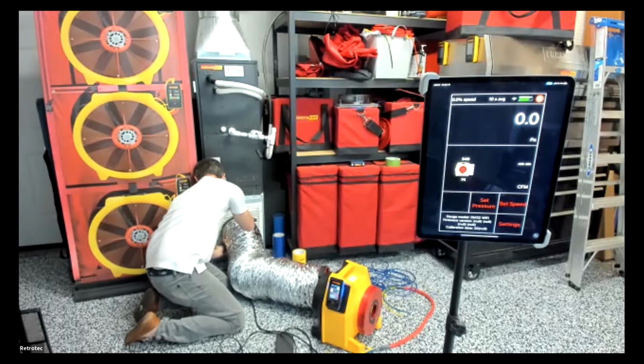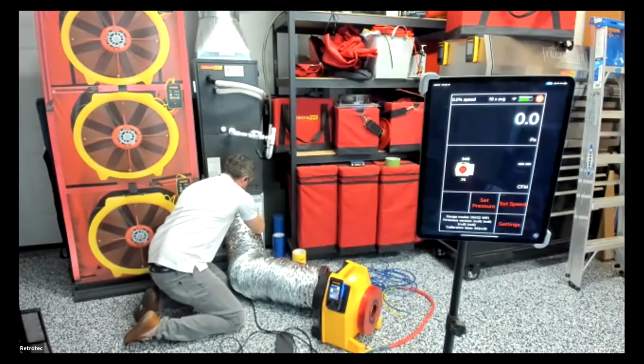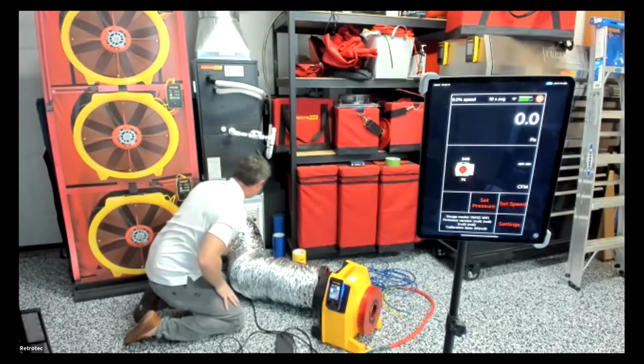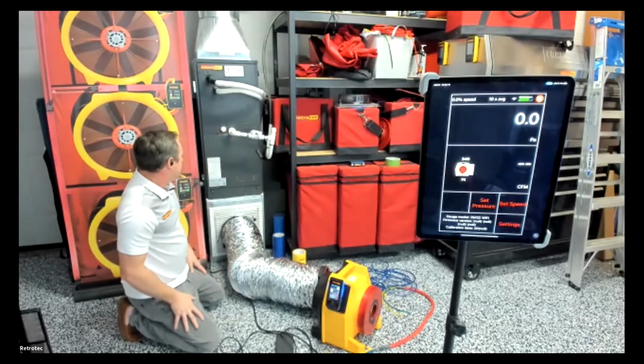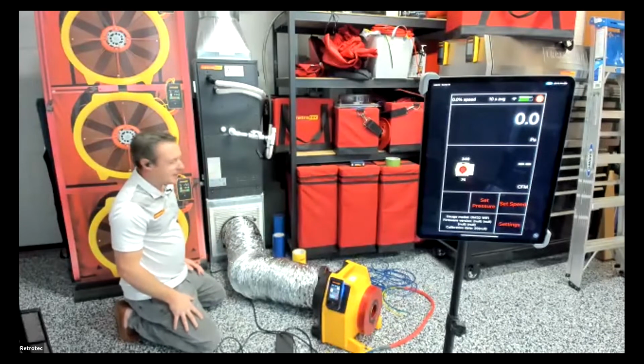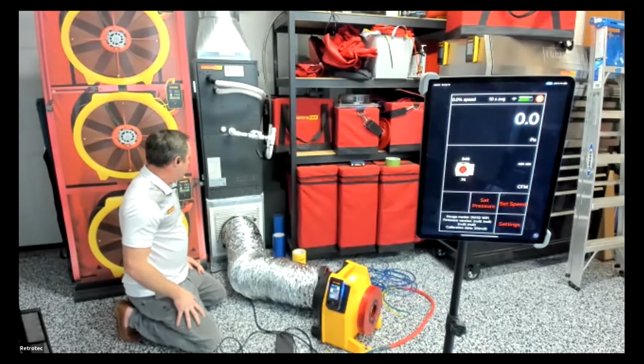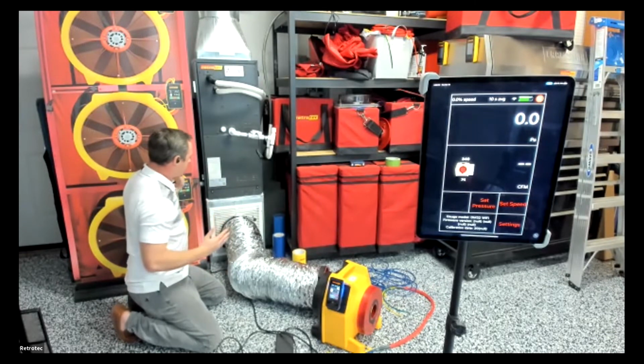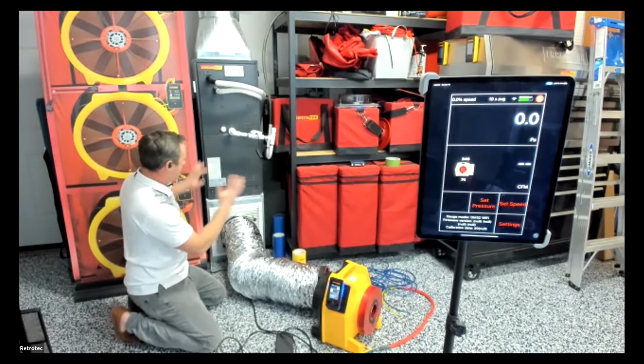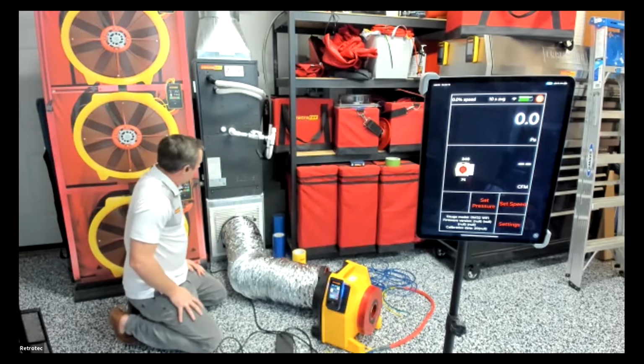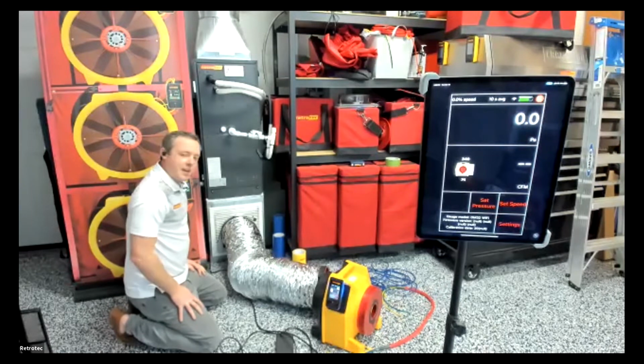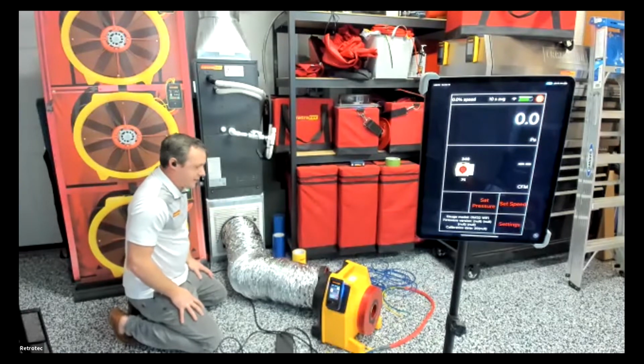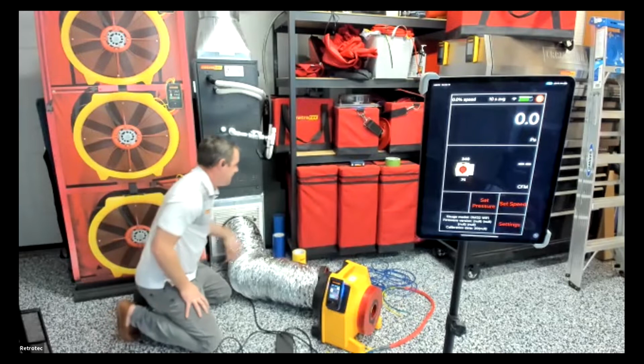There are some cases where you may want to attach this to the air handler itself. Say you don't have good return access, you can do that too. What some folks do, they'll take the service panel off and then either come up with their own panel out of cardboard or plastic, or just tape the flange in there and make sure you have a good seal. So those are the two most common ways we're going to attach this duct tester to the duct system.